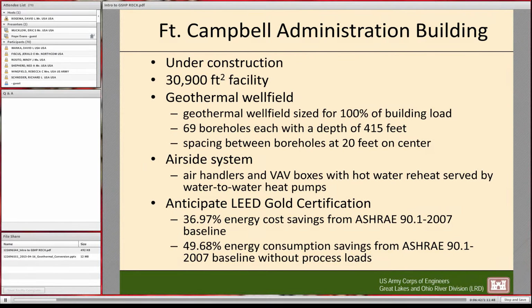It is almost 31,000 square feet. It is what we would call a full geothermal project, meaning the geothermal well field is sized for 100% of the building load, so there's no redundancy with a boiler or cooling tower. There are 69 boreholes, each with a depth of 415 feet, spaced 20 feet apart from center to center.